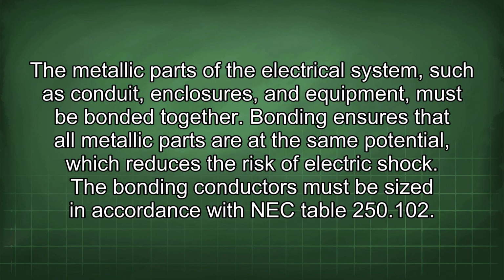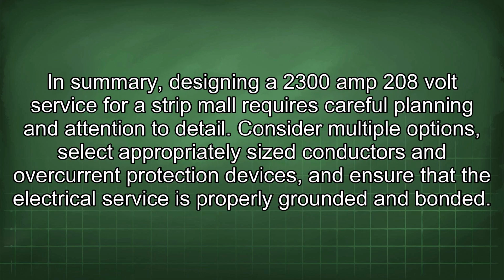The metallic parts of the electrical system, such as conduit, enclosures, and equipment, must be bonded together. Bonding ensures that all metallic parts are at the same potential, which reduces the risk of electric shock. The bonding conductors must be sized in accordance with NEC Table 250.102.